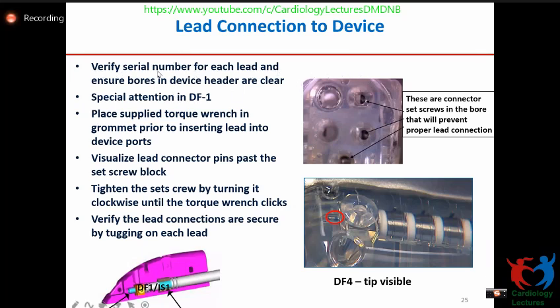Verify serial numbers for each lead and ensure both holes in the device header are clear. Special attention is needed for DF1, because with DF4 you only have one choice.